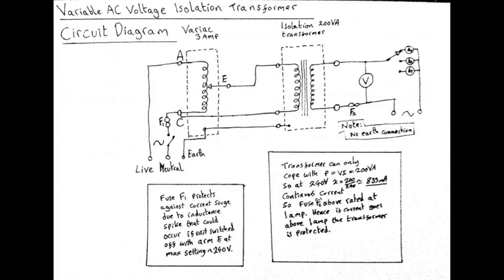But you can ignore that in terms of what's actually going on, because on the secondary side of the isolation transformer there is no connection to earth, and that's your isolation. If you look at the two outputs of the isolation transformer, I've got an AC voltmeter across, which measures the voltage between those two points. Then in series, you could select one of three ammeters.